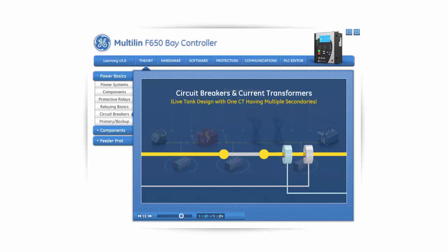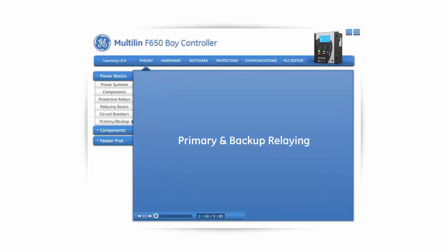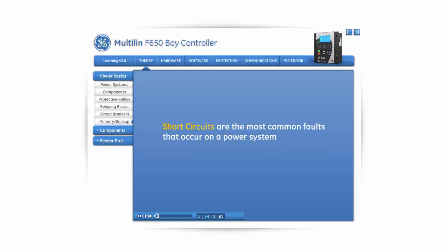With the live tank CB design, the contact enclosures are at the same potential as that of contacts, eliminating the need for insulation between them. It is, however, not possible to incorporate CTs within the bushings, as the entire CB is at line potential. In this case, the CTs have to be mounted to a separate freestanding structure, and only CTs with multiple secondary are employed. In general, the most common faults that occur on a power system are short circuits.